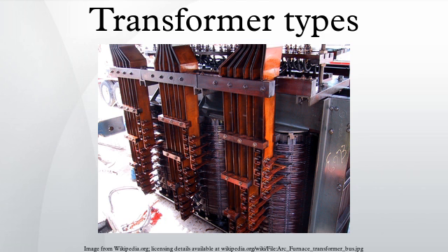Autotransformer. An autotransformer has one winding which is tapped at some point along the winding. Voltage is applied across a portion of the winding, and a higher voltage is produced across another portion of the same winding. The equivalent power rating of the autotransformer is lower than the actual load power rating. It is calculated by (1 - Vin/Vout) x load VA.